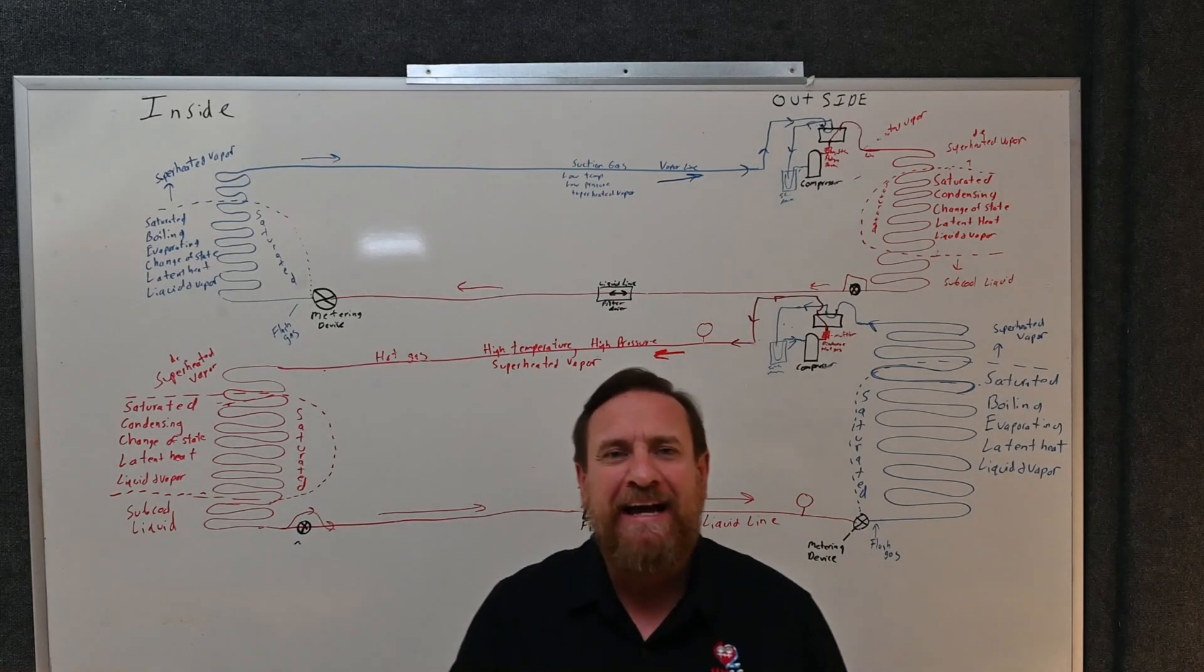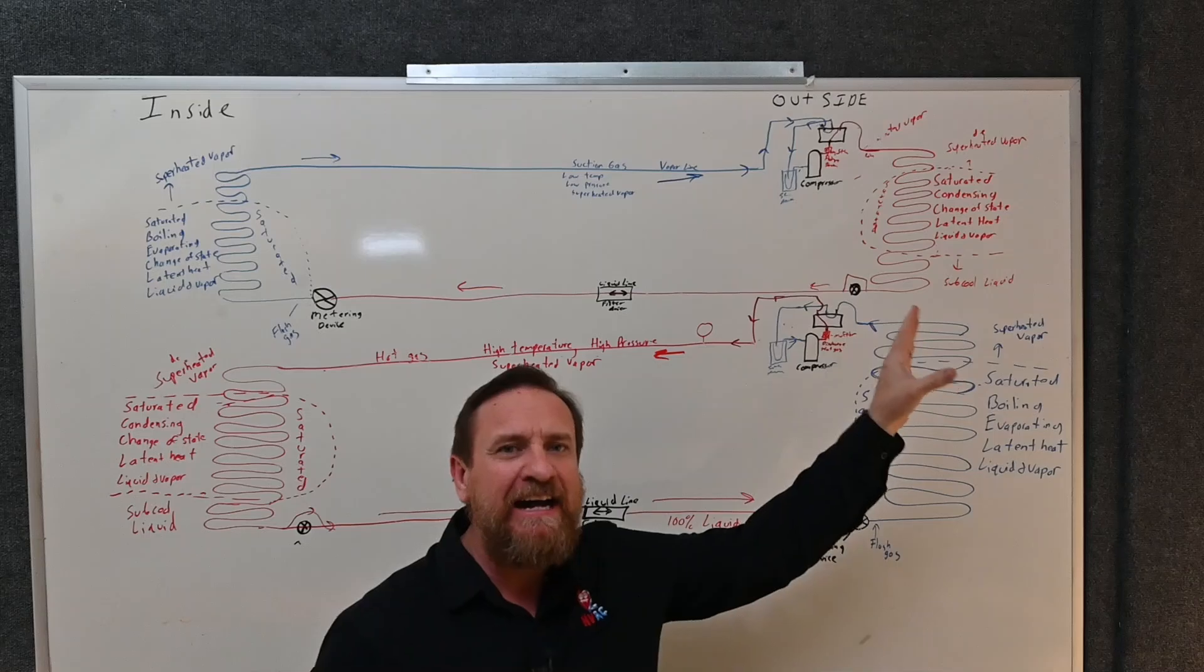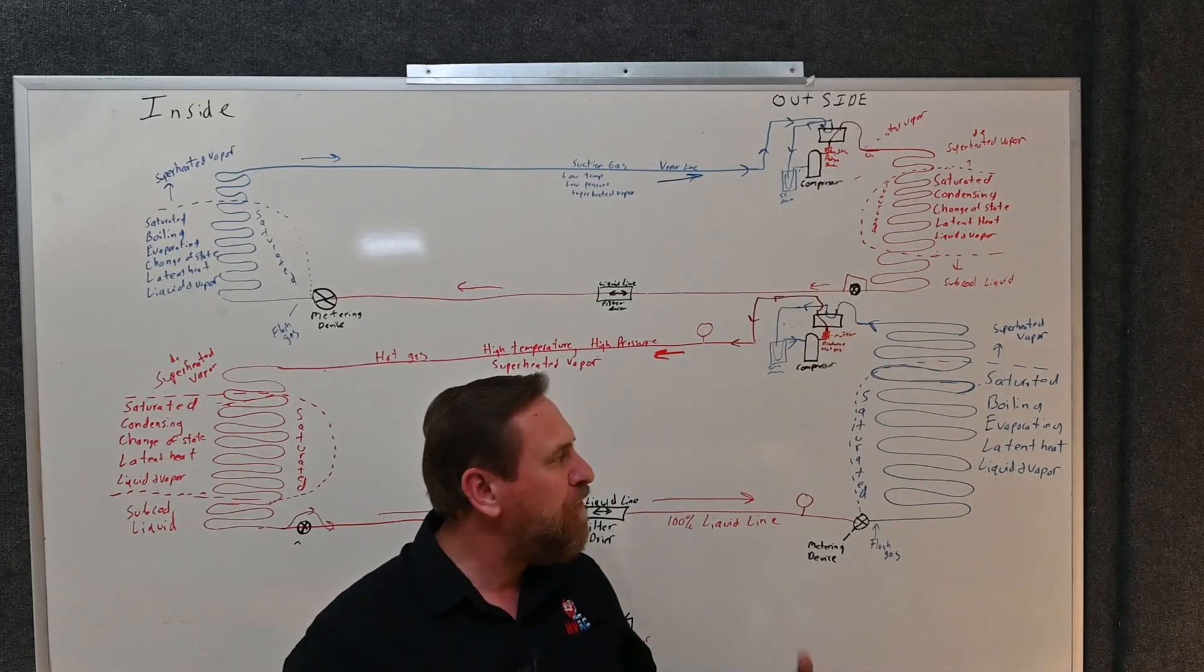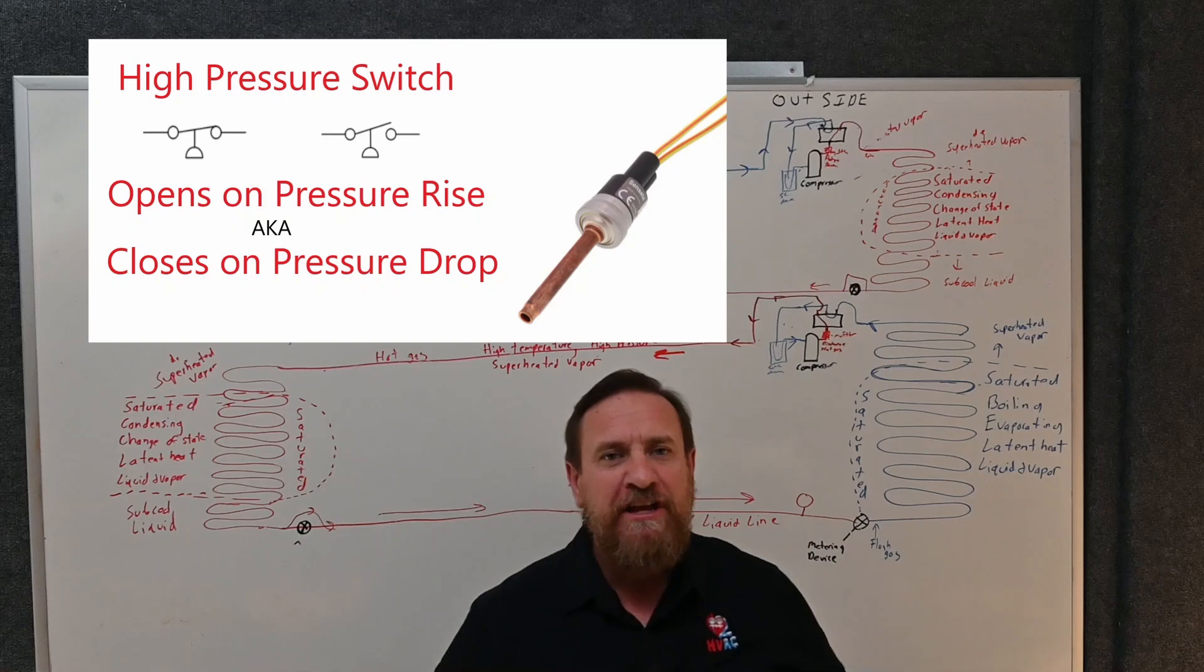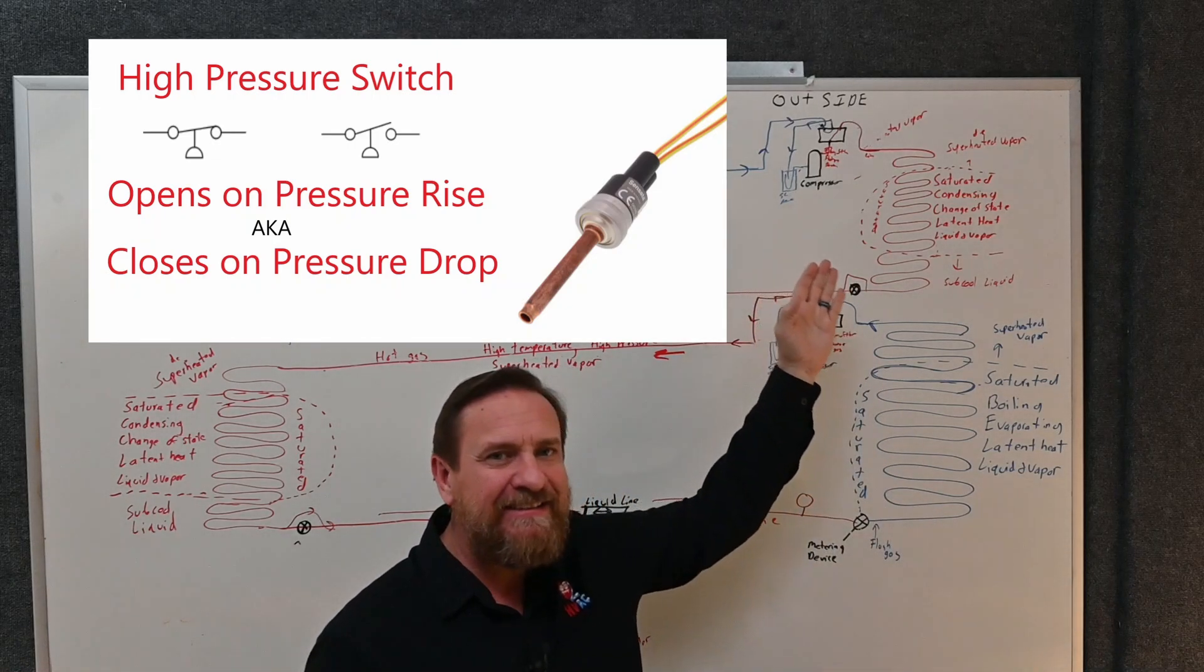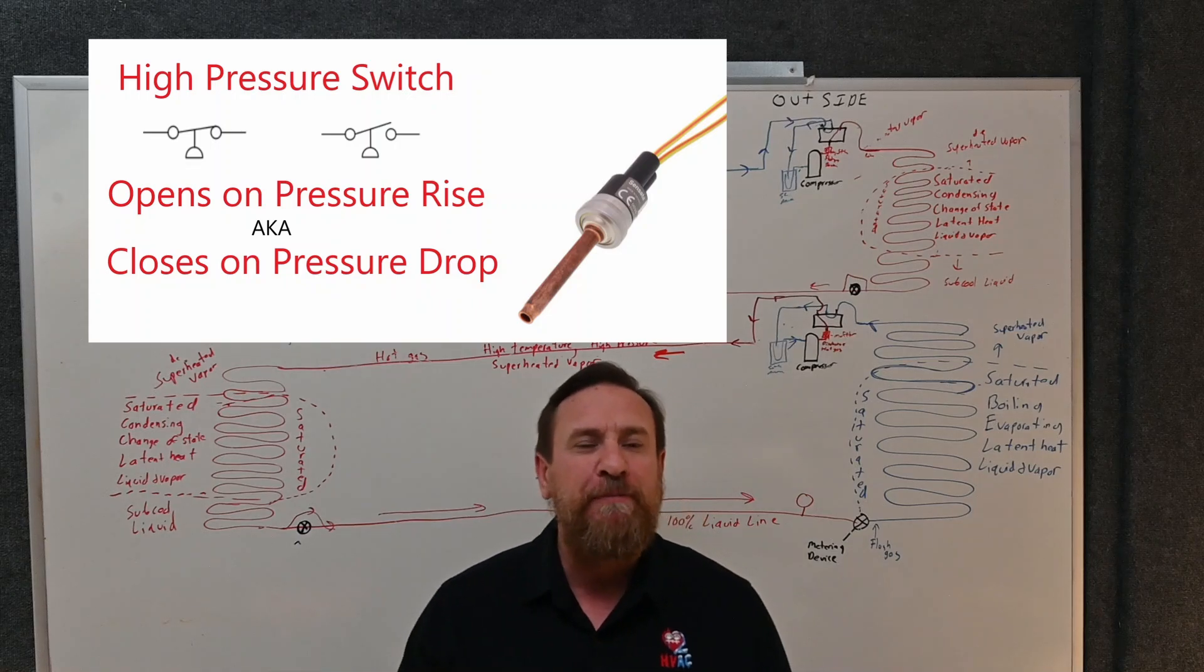Let's cover some basic heat pump diagnostic scenarios. In this scenario, it's working perfectly fine in air conditioning mode, but once we go to heating mode, we start tripping the high pressure switch. There are several possibilities we have.